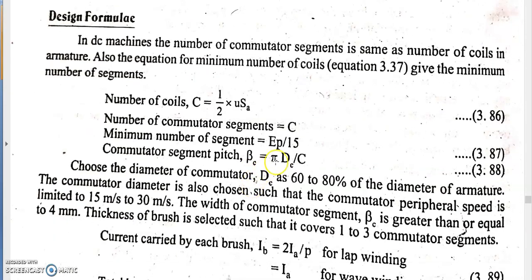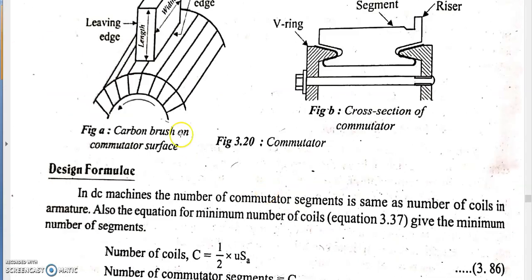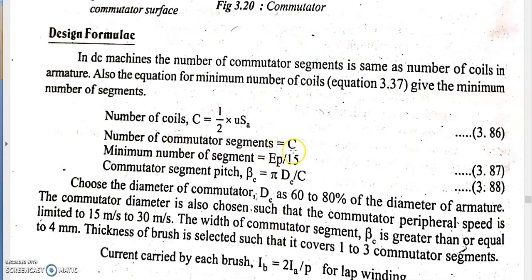The design formulas include the total number of commutator segments. The number of commutator segments is always equal to the number of coils in the machine. The number of coils is given by the equation: (1/2) × U × SA, where U is the coil sides per slot and SA is the number of armature slots. The number of armature slots has already been calculated in previous sections.